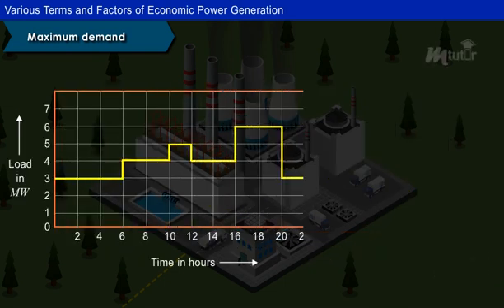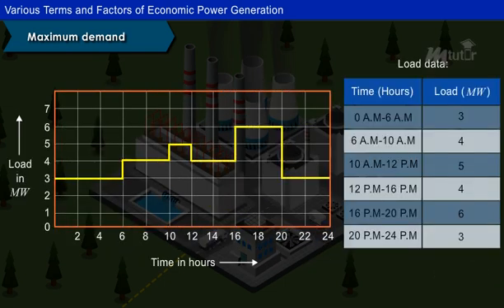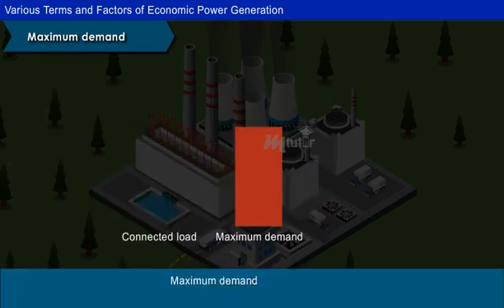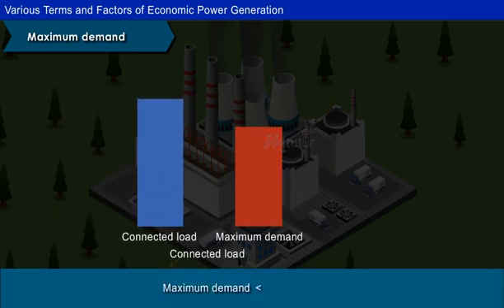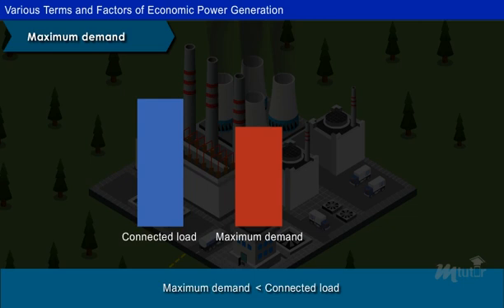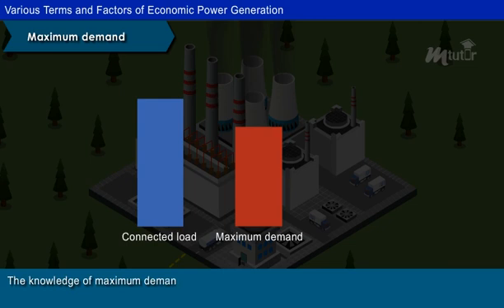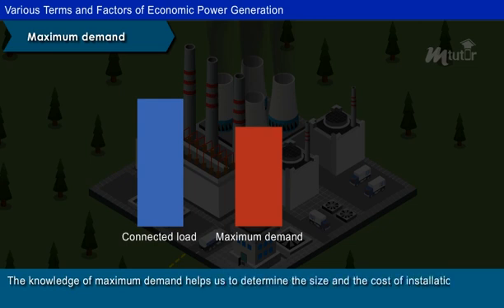For example, the load curve for typical load data of the power system is as shown. From the load curve, we can observe that the maximum demand on the power station is 6MW. The maximum demand of the power station is always less than the connected load because all the consumers do not switch on all the electrical appliances at the same time. The knowledge of maximum demand helps us to determine the size and the cost of installation of the power station.